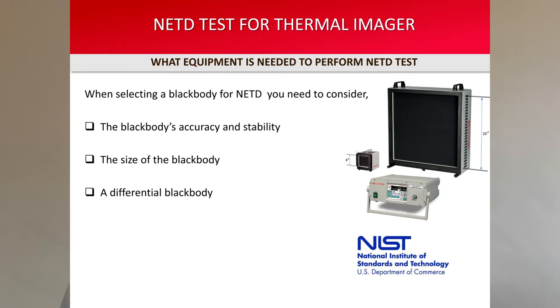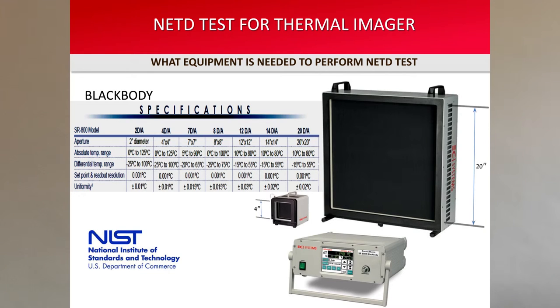When selecting a black body for NETD, you need to consider: one, the black body's accuracy and stability. Since the test is often performed with millikelvin resolution, it is important to use an accurate black body and verify that it is certified as NIST traceable — NIST stands for the National Institute of Standards. Two, the size of the black body is also important; try to select one with a large enough surface area to also perform tests like uniformity. Three, a differential black body is required for the NETD measurement, as the test is run by measuring the temperature of the black body relative to the temperature of the target, and the black body controller constantly monitors the target's temperature.